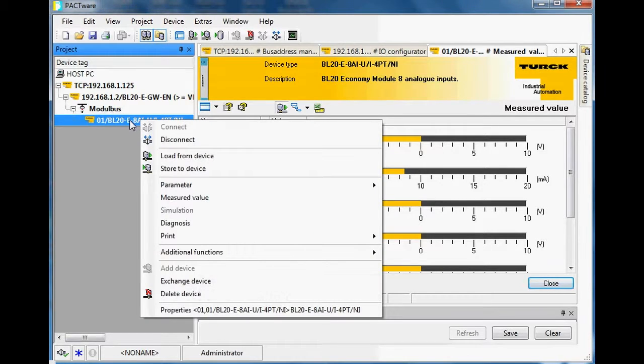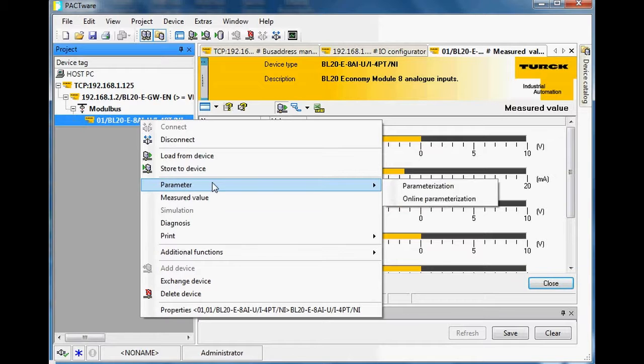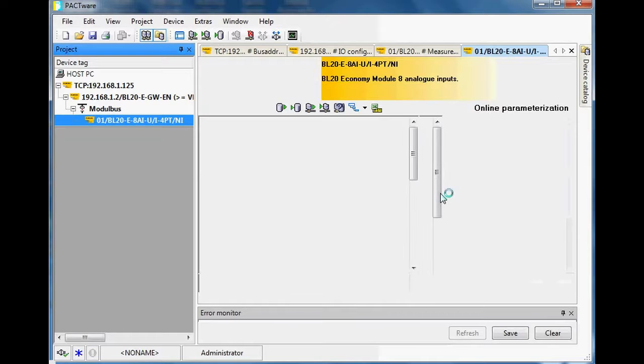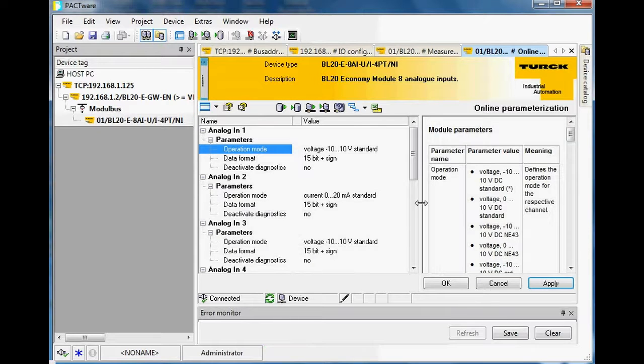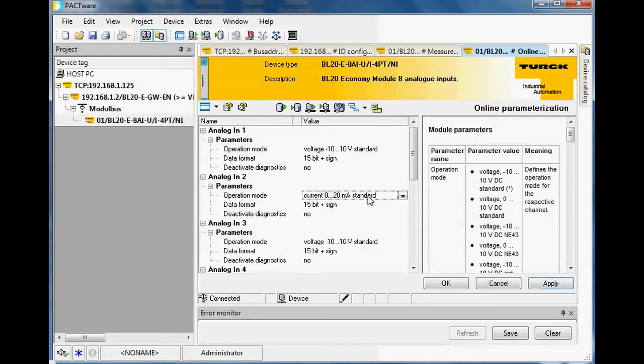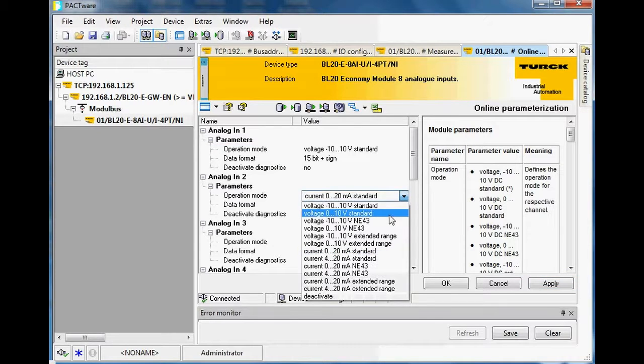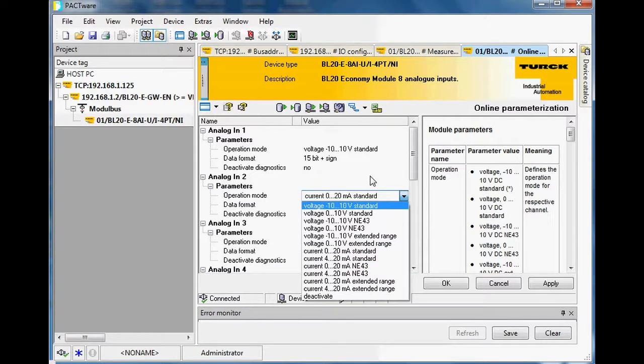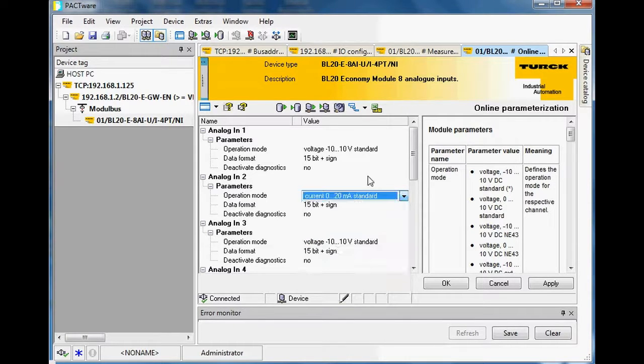Over here on the left, if I right-click on this particular card and go to Parameter, since I'm online I can go to Online Parameterization. You can see that channel two is currently set up as 0–20 milliamp. The default setting is plus/minus 10 volt, but if you hit the pull-down you can change the settings for each particular IO channel.